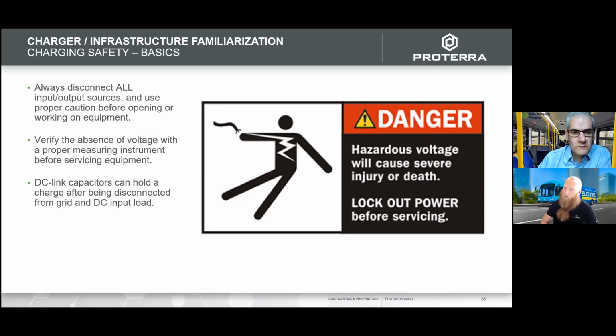As I mentioned before, in a question we answered, the DC capacitors—the inverter capacitors on our buses—hold a charge for a certain period of time. Similarly, chargers have DC link capacitors that also hold a charge for a while. For most of our charging systems, 10-15 minutes is a good rule of thumb. Typically, by the time you've locked out the input source and put on your arc flash gear, it's safe to open the charger and start verifying the absence of voltage.